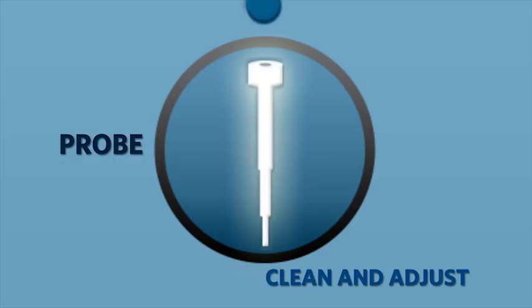Once the sample probe height has been set, run a system clean using sodium hydroxide. For detailed instructions on how to run the system clean function, use the run system clean video. This will resolve most clog and verification issues.